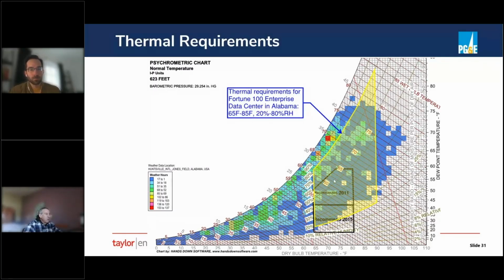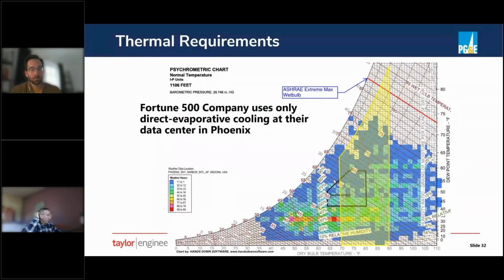Here's another client that we work with, also using only direct evap cooling at their data center in Phoenix, Arizona. They don't have any minimum humidity requirement, and their maximum humidity is also 80%. And comparing that to the ASHRAE envelope, they're also able to do all their cooling with air economizer and direct evap cooling, no mechanical cooling, even in Phoenix. So it really makes a big difference what envelope and what environmental criteria you're going to be designing and operating to. And so we're going to dig a little bit more into what's driving ASHRAE to these conditions.